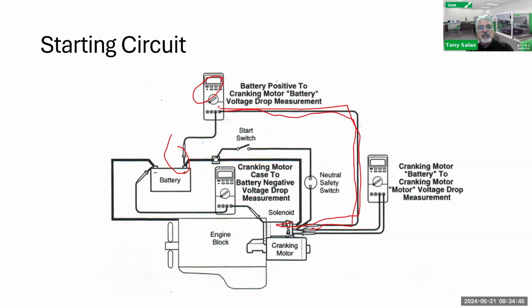Now, if you don't think this is a big deal, it is. How many times have we seen corrosion going on inside the cable? The battery cable might look nice from the outside, but if you slice it with a razor blade and look at the conductive surface inside, you'll find migration — sulfur and corrosion migrating through the whole inside of the cable. So just because it looks pretty doesn't mean it's good. Definitely do these voltage drop tests.